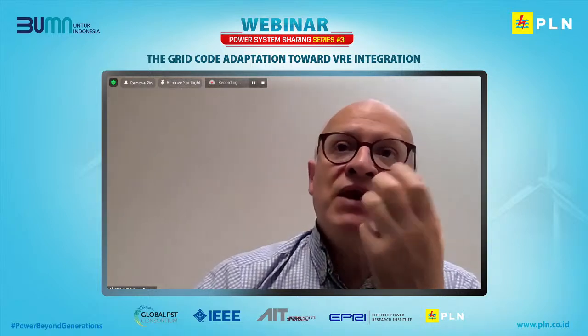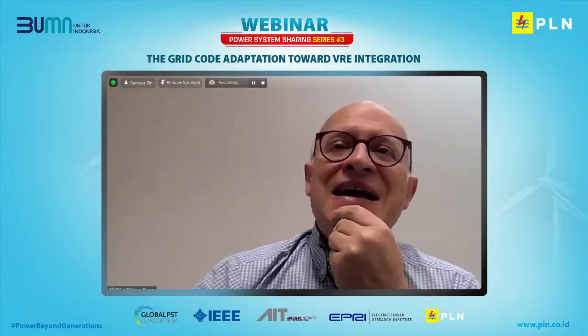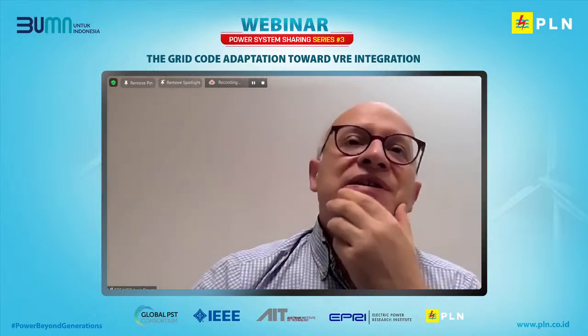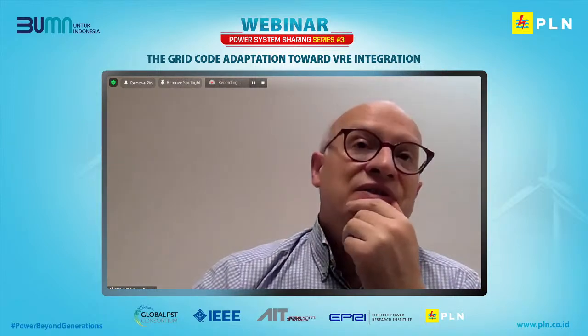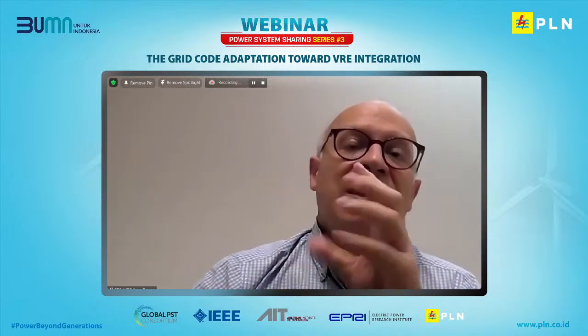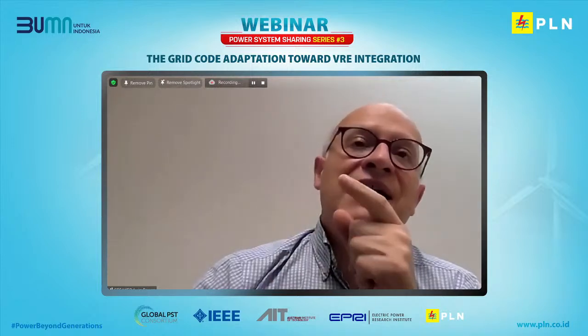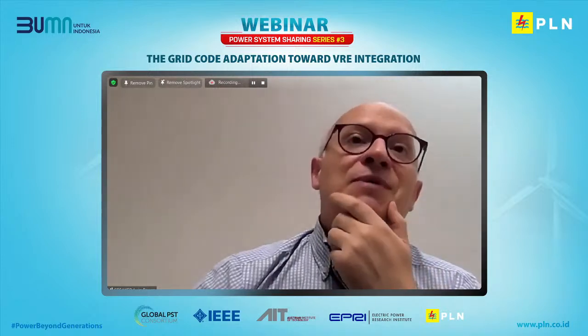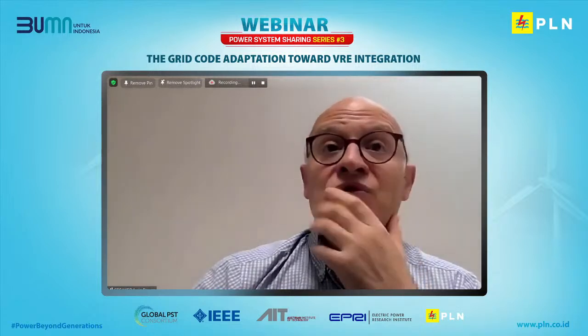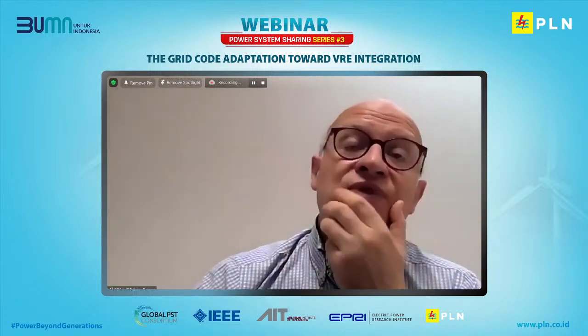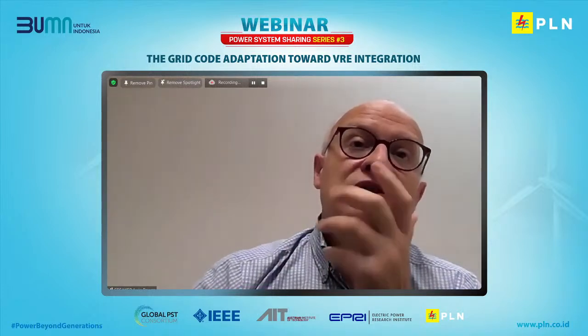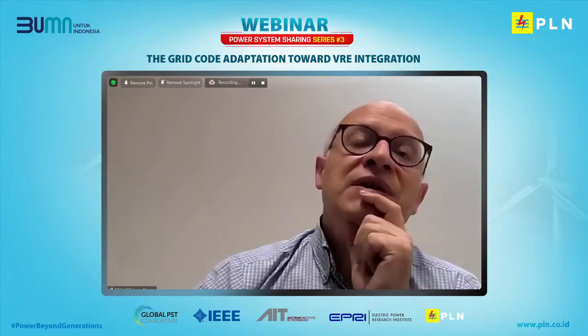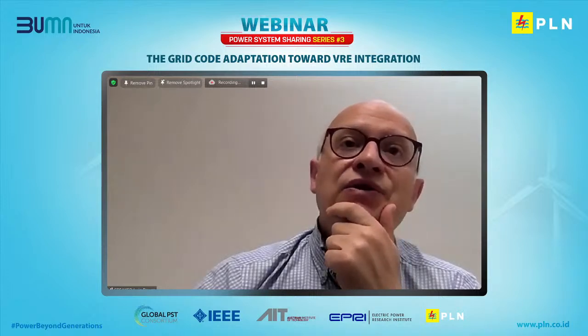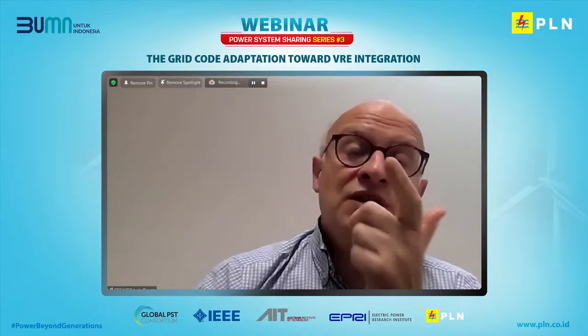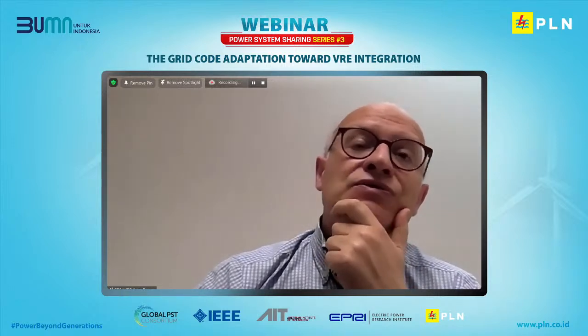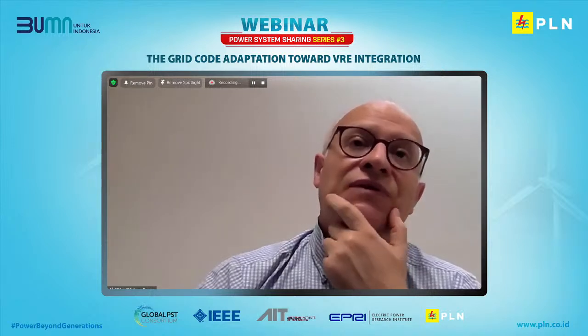Within the CIGRE working group, we have been working with manufacturers, and for other pieces of equipment, there is no constraint on the rate of change of frequency. The problem is that you have such kind of protection to detect a condition, so that there is a wrong application of the rate of change of frequency. Of course, as we are losing inertia, rate of change of frequency will be bigger. But it is very important to promote that the detection of islanding conditions in distributed generation and inverter-based generation is not done using a protection based on rate of change of frequency.